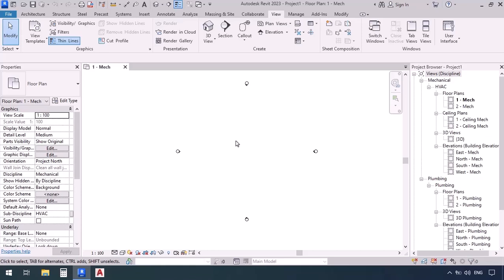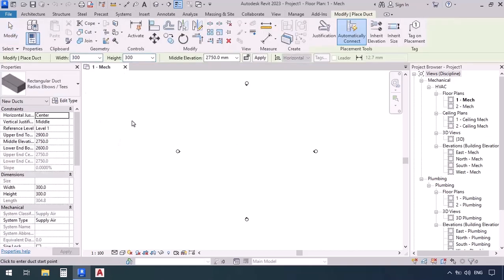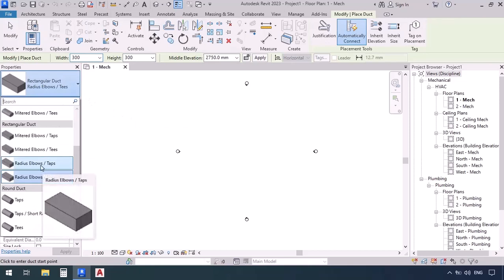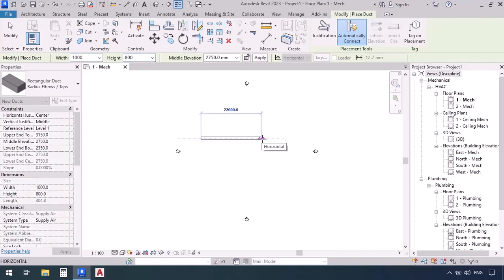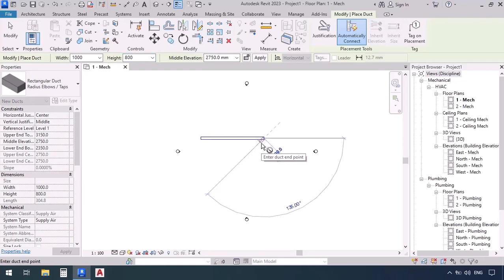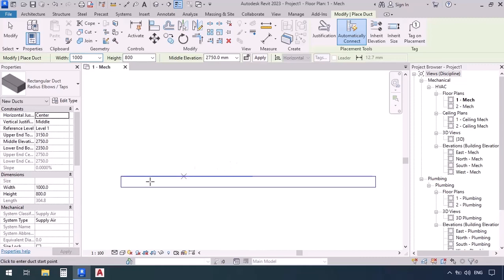I've opened a mechanical template. I go to the systems tab, then the duct command. We will be starting by drawing a canal, using ducts with the fitting type radius elbows taps, with the system type supply air as default. For the width we're going to enter 1000, height 800, and for the elevation we'll keep it 2750. First click and then the second click, then escape — so now we've drawn one piece of duct.